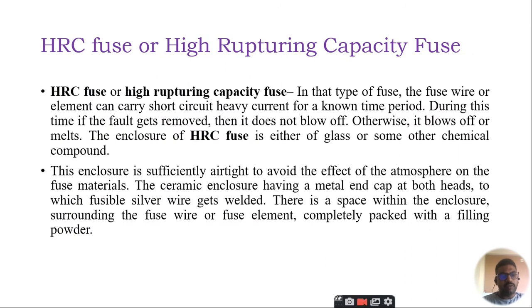For higher versions, we have the concept of HRC - High Rupturing Capacity fuse. In HRC fuse, the fuse wire or element can carry short circuit heavy current for a known time period. During this time, if the fault gets removed, it does not blow off; otherwise it blows off.